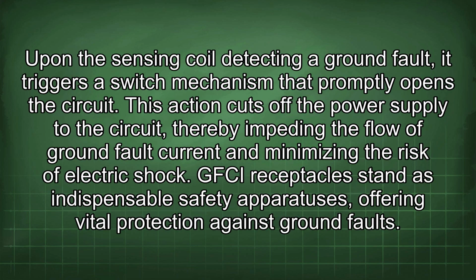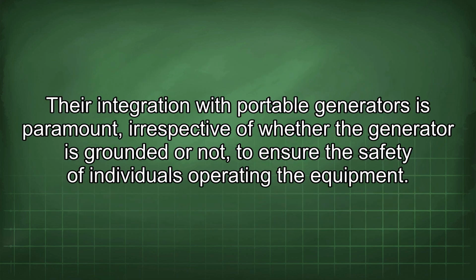Upon the sensing coil detecting a ground fault, it triggers a switch mechanism that promptly opens the circuit. This action cuts off the power supply to the circuit, thereby impeding the flow of ground fault current and minimizing the risk of electric shock. GFCI receptacles stand as indispensable safety apparatuses, offering vital protection against ground faults. Their integration with portable generators is paramount, irrespective of whether the generator is grounded or not, to ensure the safety of individuals operating the equipment.